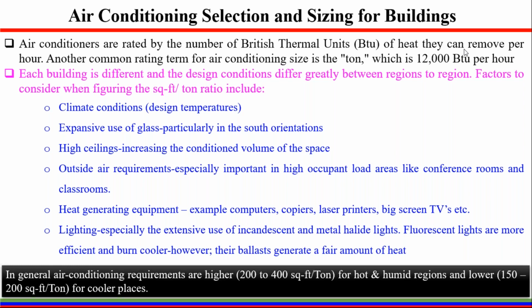Outside air requirements, especially when there are occupant loads, because the outside air temperature can directly affect the conditioned zone. Heating equipment: which equipment is being used in the conditioned space? Computers, fax machines, or is there a refrigerator or a TV placed there? That should be kept in mind. Lighting can give another heating load, because every light produces heat, and that heat is a burden on your air conditioning system, because the system has to cool down that heat also.